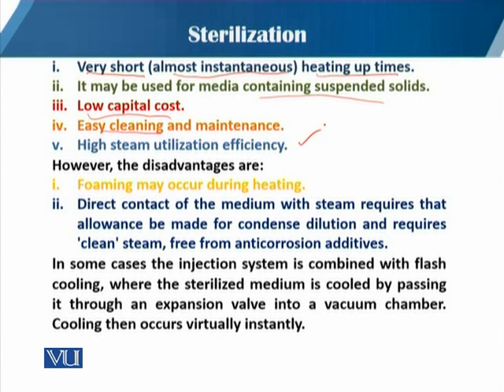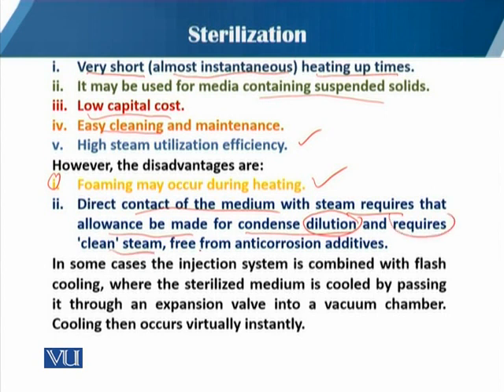However, there are disadvantages. The first is that foaming may occur during heating — when you are directly blowing steam into the medium, there is excess foaming. On the other hand, direct contact of the medium with steam causes condensation, so allowance must be made for dilution of the medium. It also requires clean steam, as direct steam may contain particulates or heavy metals.